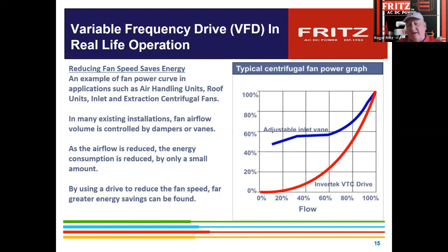And what's happening in Europe is a lot of the motors now, they've also figured out that when you put a VFD on a regular induction motor, at anything below 70%, the motor efficiency starts decaying. So over there, they're in version 4 of premium efficient motors, where they actually have permanent magnet rotor motors. And we're being a lot involved in implementing new permanent magnet motors, similar to what the ECM motors are. Those are a DC motor that's rectified power from AC with controllers on them. Again, because you get better torque control of the motor below 70%. And so you see about an extra 10-15%.